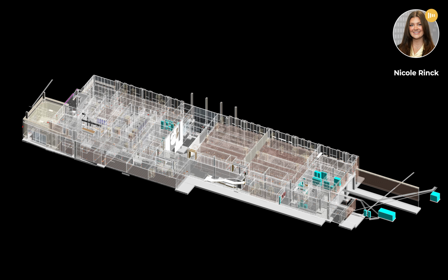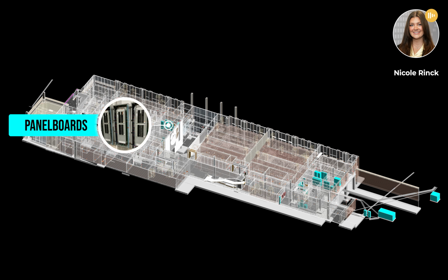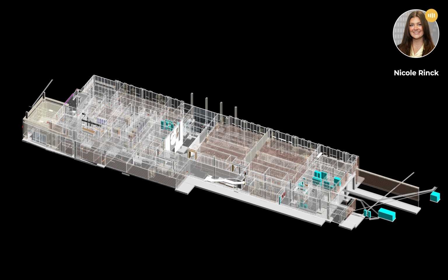Power is distributed from the main switchboard to branch panel boards. When placing branch panel boards on a floor plan, you should consider locating them close to the loads they will be serving. Typically, they can serve loads within a 100-foot radius. The panels are wall-mounted and need to maintain 3 feet of clearance in front. Typically, they are located in dedicated electrical closets, but they can be in public areas if they are locked.